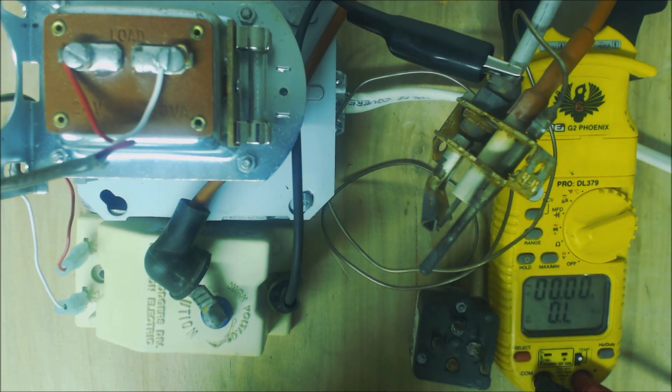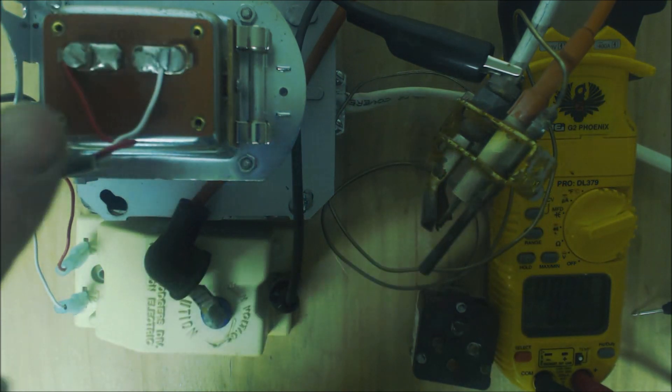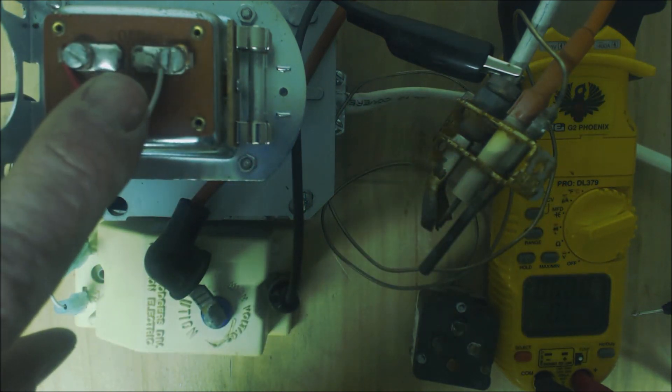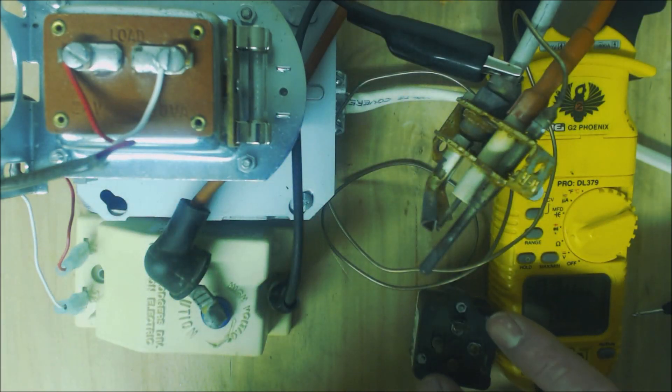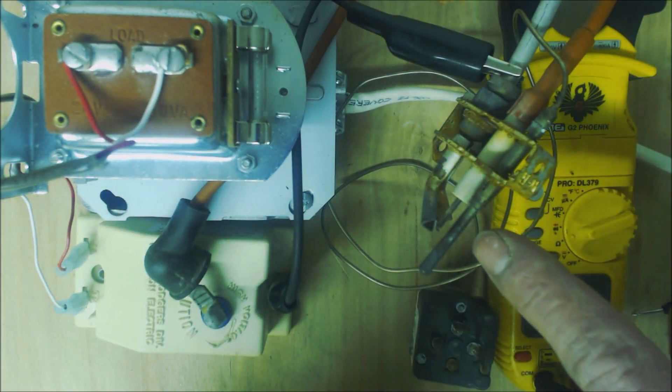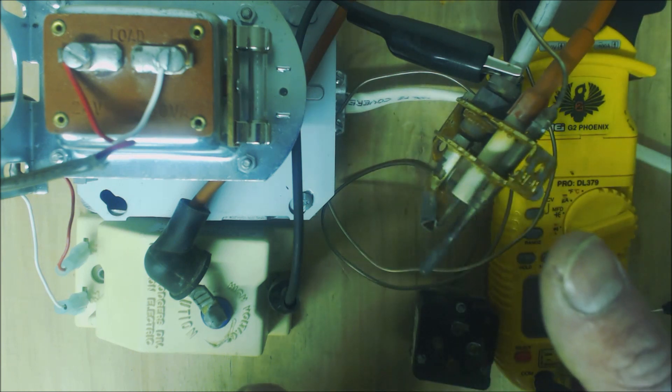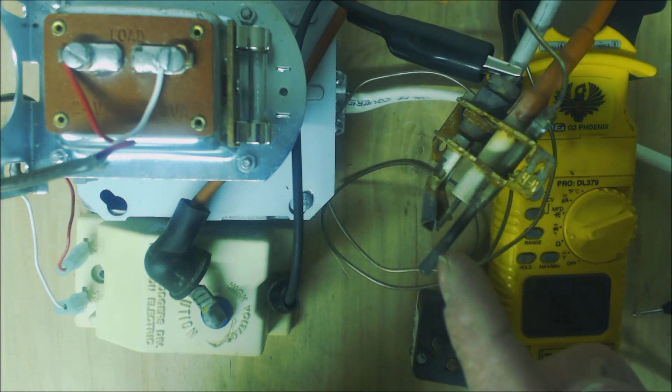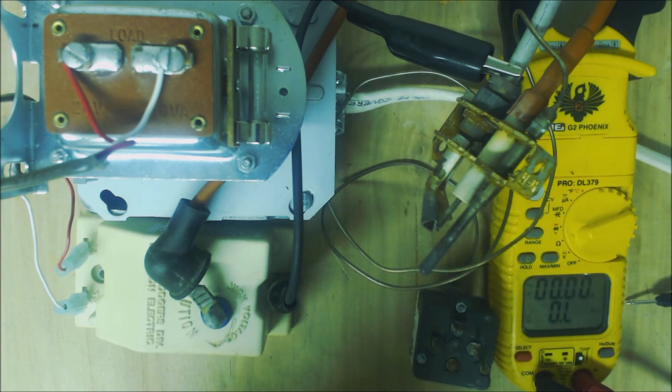I'm going to first power this pilot relight directly off the transformer, and then wire into the mercury flame sensor and heat this with a torch, just like it's normally wired in the field. First though, I want to show you what that spark looks like when you directly power the pilot relight with 24 volts.